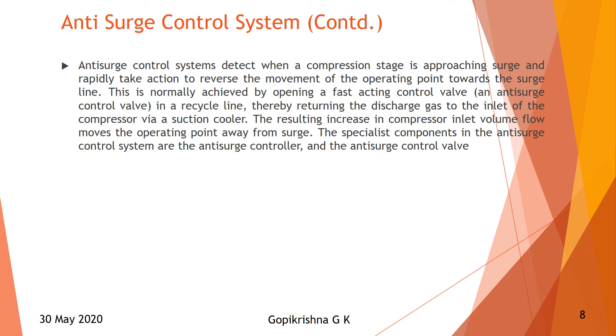Anti-surge control systems detect when a compressor stage is approaching surge and rapidly take action to reverse the movement of the operating point towards the surge line. This is normally achieved by opening a fast-acting control valve in a recycle line, thereby returning the discharge gas to the inlet of the compressor via a suction cooler. The resulting increase in compressor inlet volume flow moves the operating point away from the surge line. That is why there is a cooler — once cooled, the volume is returned to the compressor using the anti-surge control valve back to suction.